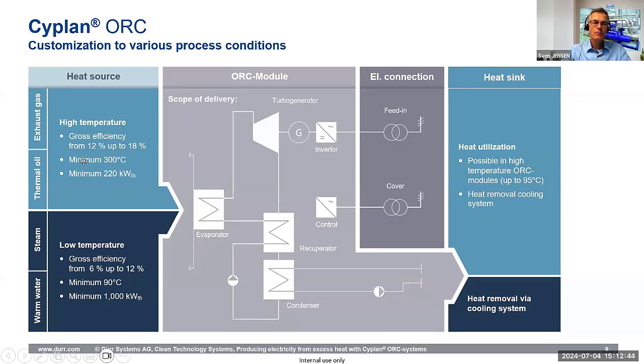When we talk about high temperature applications, we have thermal oil at 300 degrees, for example, or exhaust gases at 500 degrees. Then we can run this central gray area differently. We can operate the condenser at elevated temperatures, 90 up to 95 degrees Celsius, and then connect on this side not a cooling tower but a hot water loop. So basically all the condensing heat we need to extract from the ORC, we can push into a heating system, or it can be used for other purposes. This is quite important for industrial applications, which I'll explain in some further slides later.